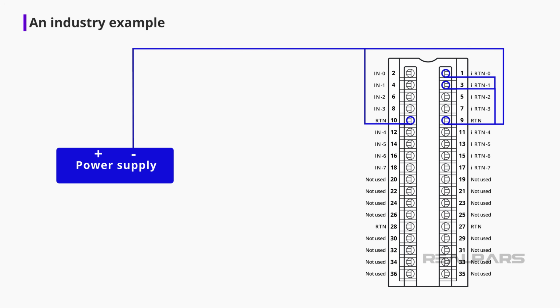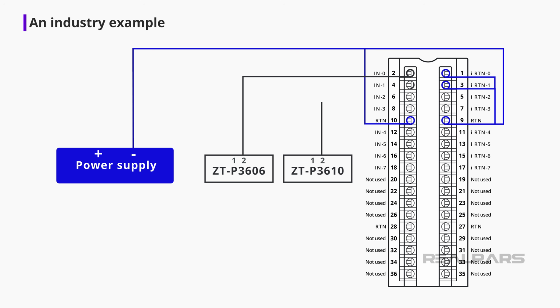Field wiring diagrams vary between companies. In this example, two channels of the 1756-IF8 are wired in single-ended mode. Pressure transmitter ZT-P3606 is connected to channel 0, and ZT-P3610 is connected to channel 1. Both transmitters share the same positive 24-volt DC power supply.